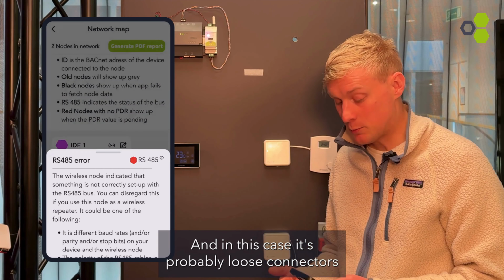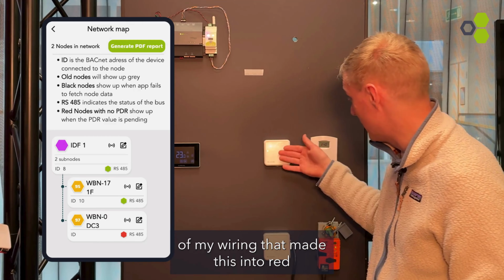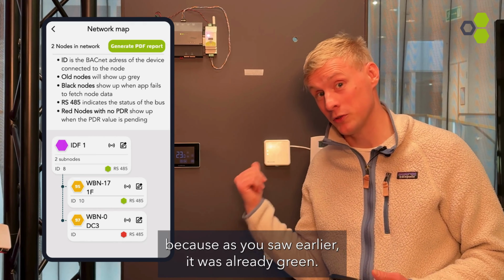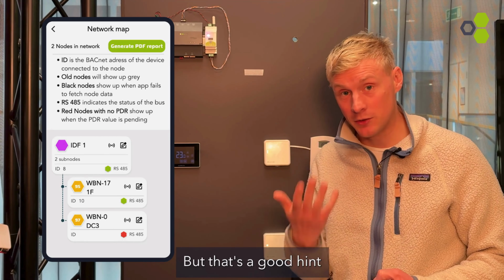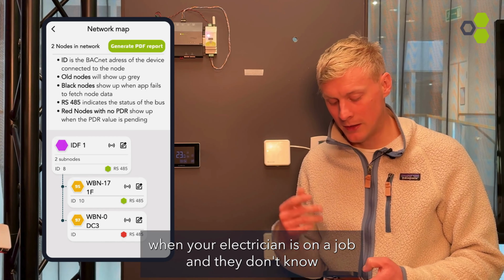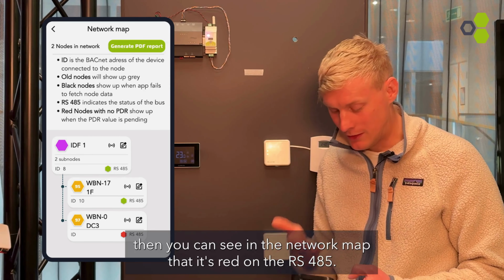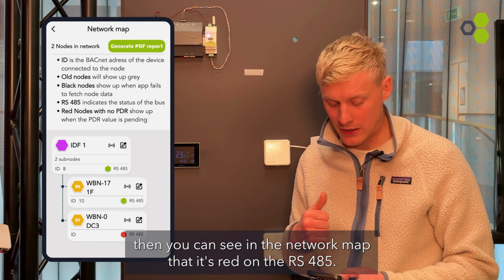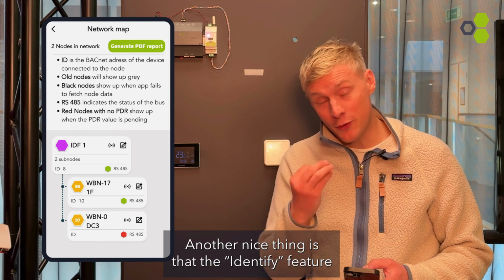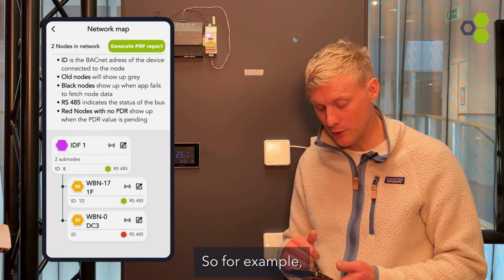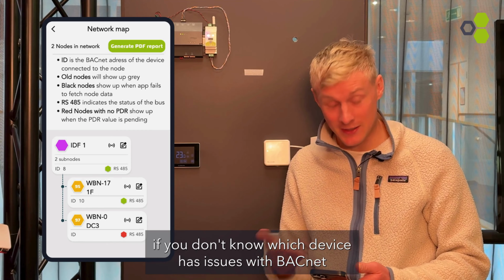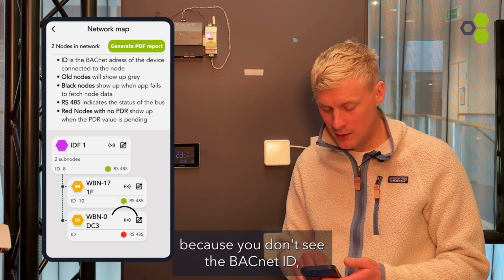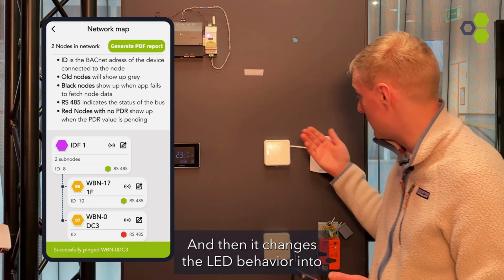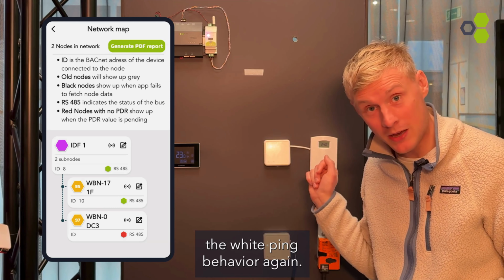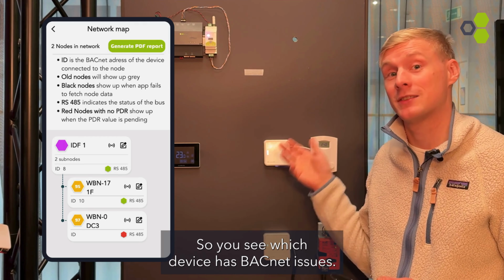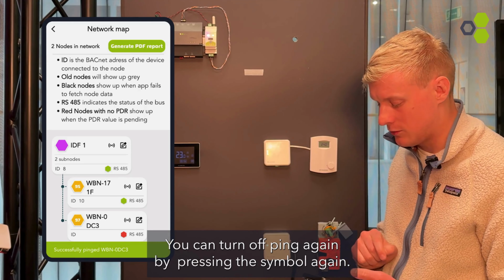And in this case, it's probably loose connectors in my wiring that made this red, because as you saw earlier it was already green, so it's probably wiring issues. But that's a good hint when your electrician is on a job and they don't know why the BACnet device is not connected. Then you can see in the network map that it's red on the RS-485. Another nice thing is that the identify feature, the ping feature, is also now in the network map. So for example, if you don't know which device has issues with BACnet, because you don't see the BACnet ID, you can press identify there, and then it changes the LED behavior into the white ping behavior again. So you see which device has BACnet issues. You can turn off ping again by pressing the symbol again.